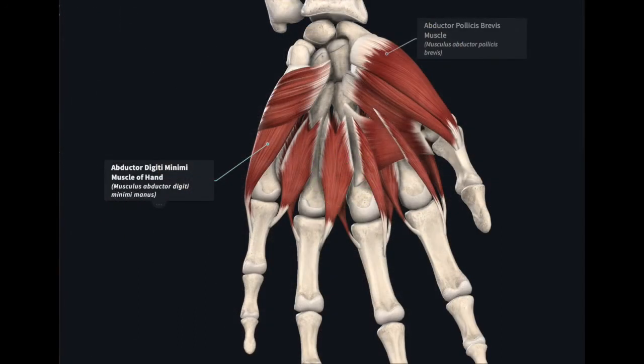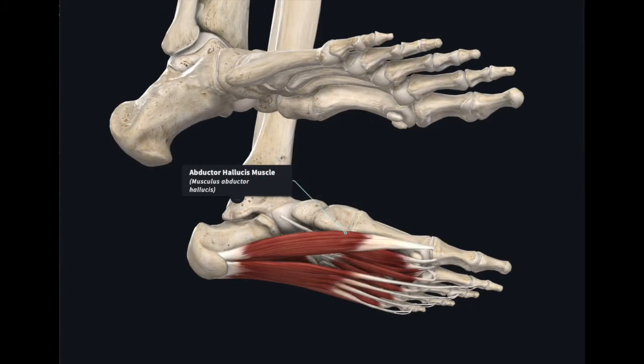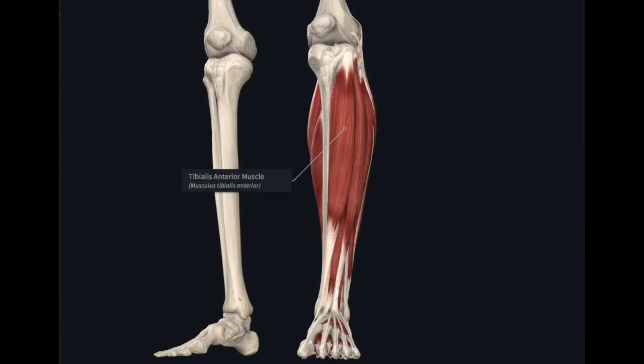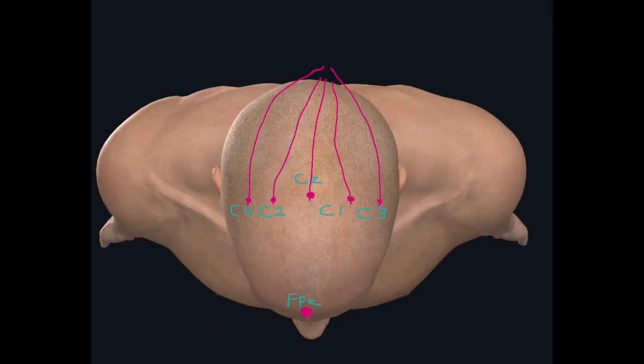Paired subdermal needle electrodes are placed in distal muscles of the upper and lower extremities for recording. Theoretically, motor evoked potentials can be recorded from any muscle. Here are three head lead stimulation needle electrode montages: C3-C4, C1-C2, and CZ-FPZ.